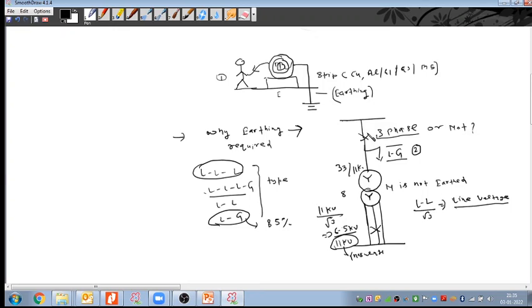And if this is a three-phase symmetrical fault, right? We can divide faults into two types, symmetrical and unsymmetrical, or asymmetrical, faults. This comes under the symmetrical faults, and this comes under the asymmetrical fault category. For this kind of fault, earthing and grounding will not play any role. What can earthing do? Earthing is only for equipment and human protection. Yes, we can do that, but neutral grounding plays no role in that.